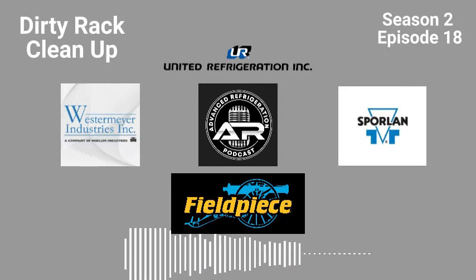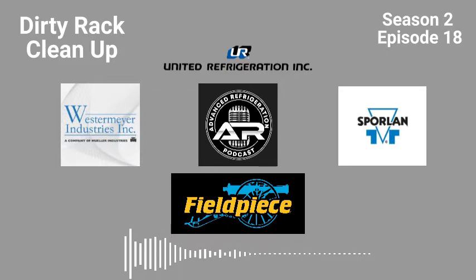Yeah, but even then, that happened there. But the majority of these stores I see, especially older independents, older stores, are so neglected with the discharge temps. PMs with discharge temps are super important. You can use that Copeland mobile app and type in your conditions, your return gas temps, your suction pressure, your discharge pressure. It'll tell you within about 10 degrees what your discharge temp should be.